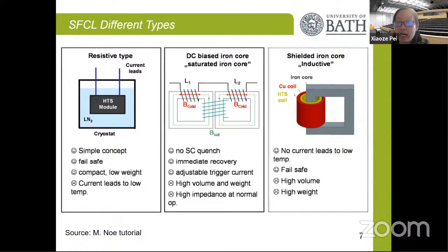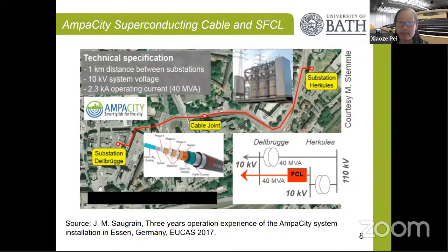There is also another inductive fault current limiter, which is the shielded iron core. The key advantage is that it doesn't require current leads to the low temperature. However, it does have the iron core structure, which means the whole unit could be quite heavy. So in the talk today, we are going to mainly focus on the resistive type of fault current limiter. We look into this because we are looking into transportation electrification, so we really want to keep the unit very compact and lightweight with high power density.